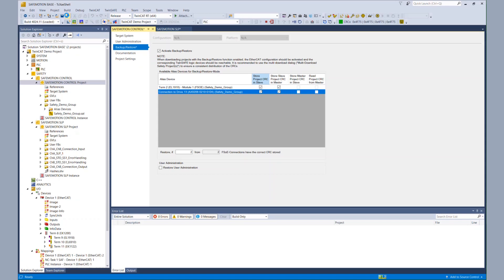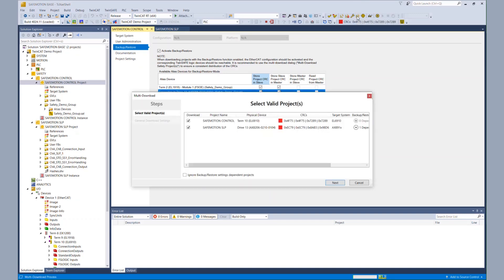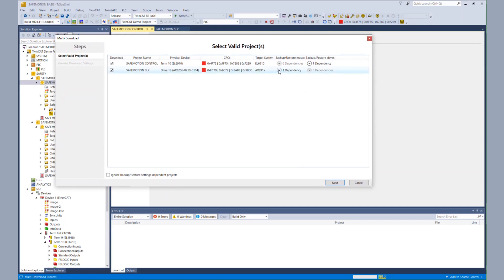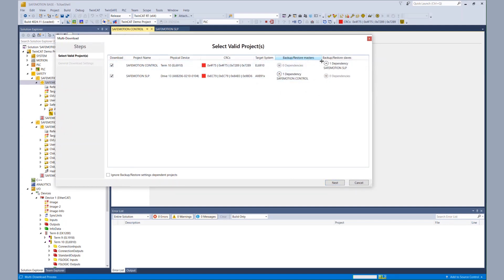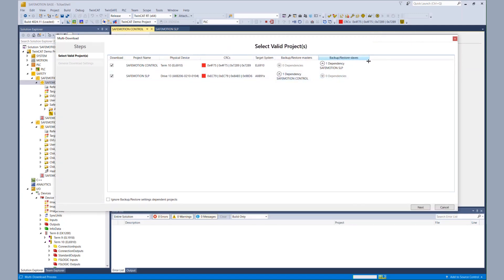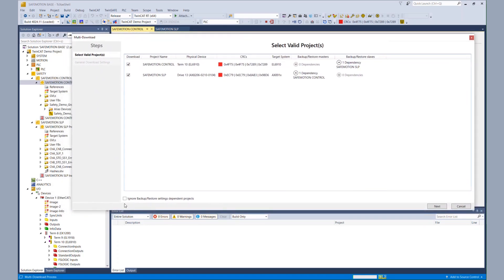That was basically all the configuration. We go to our multi-download because it also displays the dependencies between our safety projects. We can see that each project is dependent on the other project, and the wizard checks those dependencies. But I can also ignore those dependencies via the checkbox below. So I can also download only one project, but then I don't have a consistent configuration. So we take both projects.